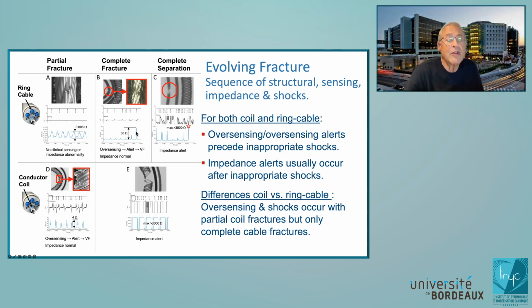You only see this much change when the entire conductor is completely fractured, and we can see that. It's hard to see that complete fracture here on the X-ray, but if we do a photomicrograph, you can see this is completely gone. The reason the impedance doesn't go to 3,000 is that all of these cables have an inner insulation around them. And as long as you don't break this inner insulation, it's a lot like the Teflon in your frying pan, very thin and sturdy, you don't get an impedance increase that you can clinically detect. And it's only when you see these impedance increases that it means the ends of the conductor have completely separated.